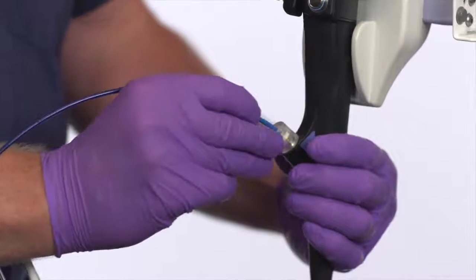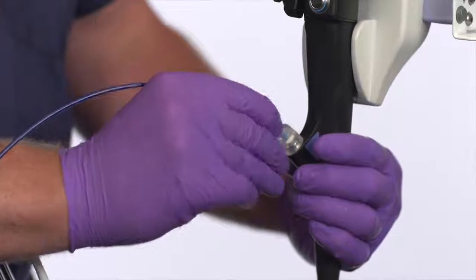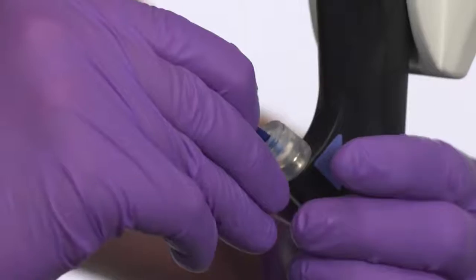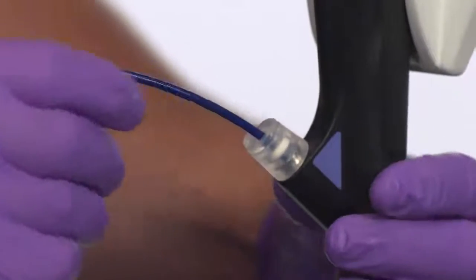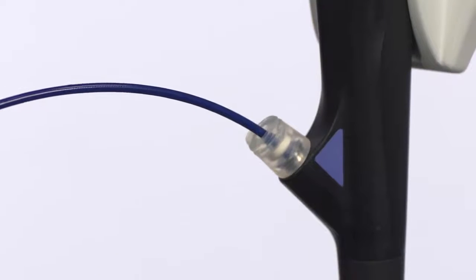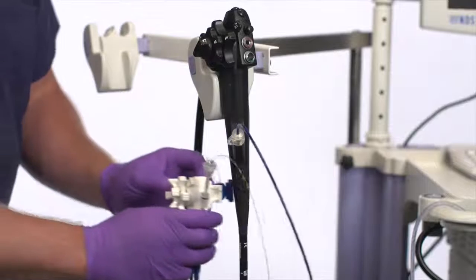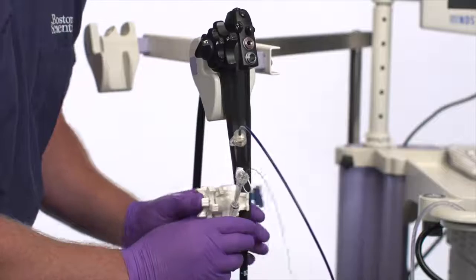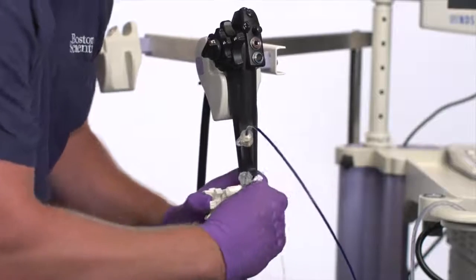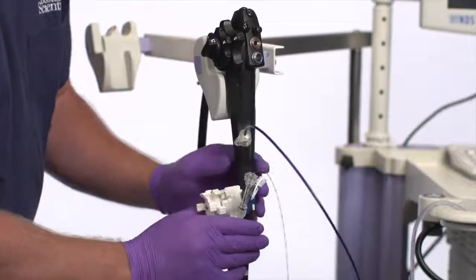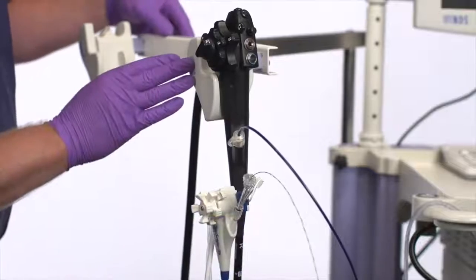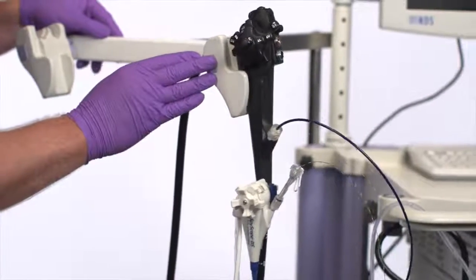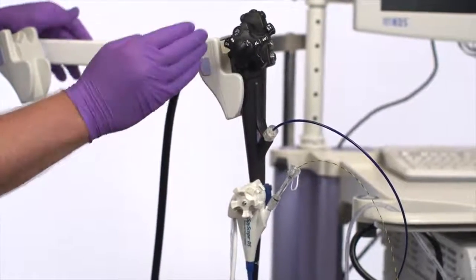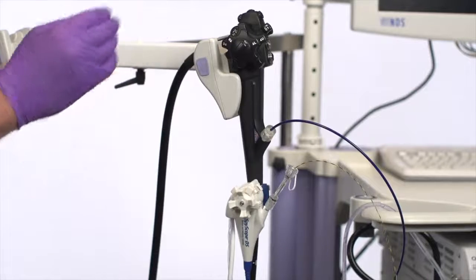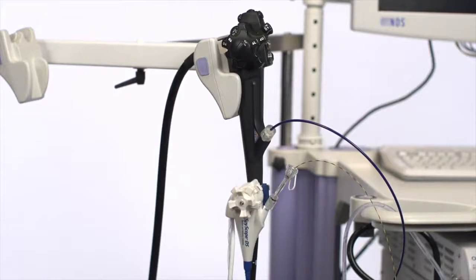If using a non-guide wire approach, insert the distal end of the SpyScope DS catheter into the working channel of a duodenoscope using short strokes, 2 to 3 centimeters. Position the SpyScope DS catheter and use the attachment strap to secure the SpyScope DS catheter to the duodenoscope. Align the articulation control knobs with the duodenoscope steering knobs, and the handle is below the duodenoscope's working channel.